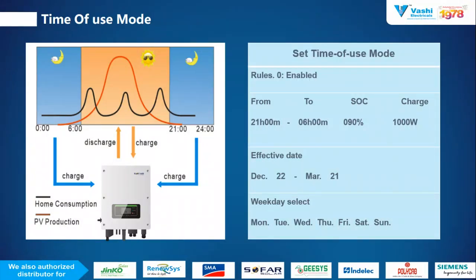When the load consumption is low, at that time you store the power in the battery, and whenever load consumption is high, you can take power from the battery or PV for the load. So this is all about the time of use mode, and in this graph it also shows the peak power when it is summer, and during the winter or night time the load consumption is low, so we use the power from the battery for the night time.